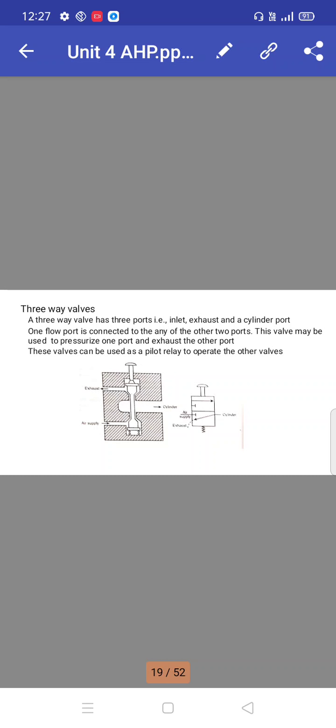Three-way valves: a three-way valve has three ports - inlet, exhaust, and cylinder port. One flow port is connected to any of the other two ports. This valve may be used to pressurize one port and exhaust the other port. These valves can be used as a pilot relay to operate other valves.